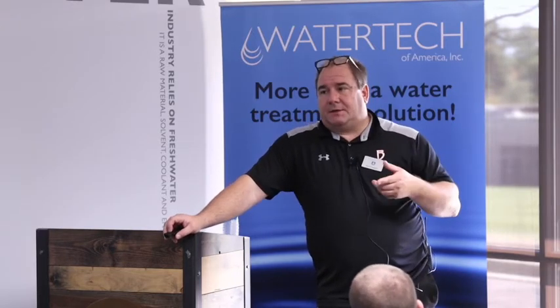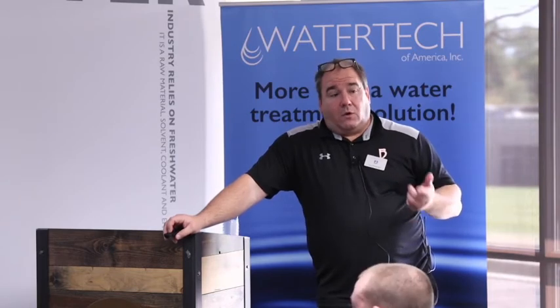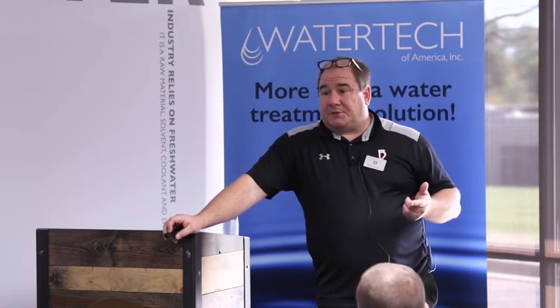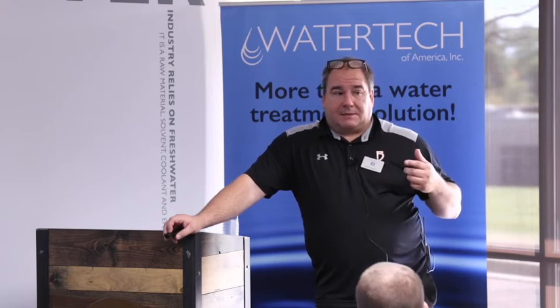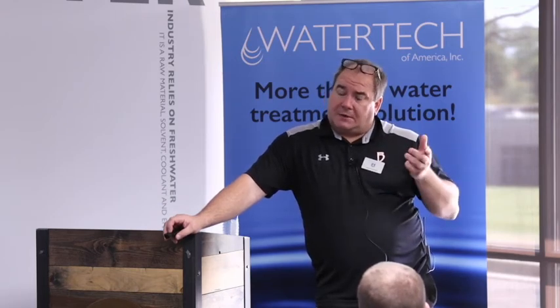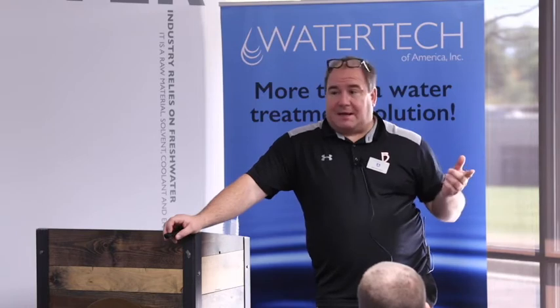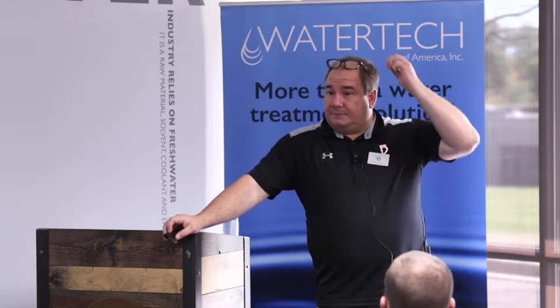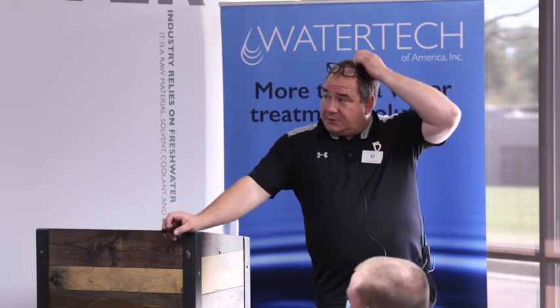So they're stuck in the deaerator, or you're not generating enough pressure and temperature to allow the gases to get out. So then now the temperature of the water is not hot enough to drive off the oxygen. So it's kind of a double-edged sword, right? And we'll show you some pictures of that.